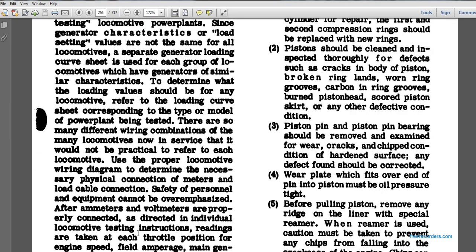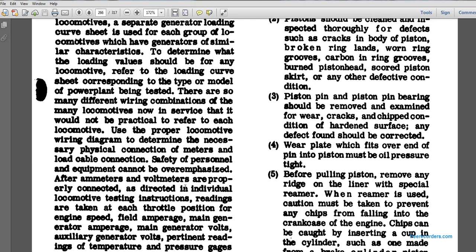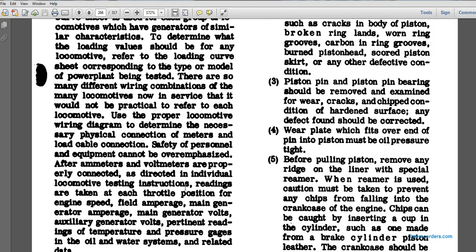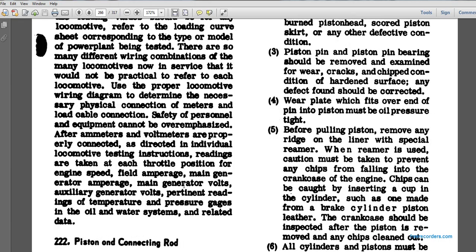After ammeters and voltmeters are properly connected, as directed in individual testing instruction readings are taken at each set throttle position for engine speed, field, armature and main generator voltage, auxiliary generator volts, and pertinent readings of the temperature and pressure gauges of oil and water systems, and related data.